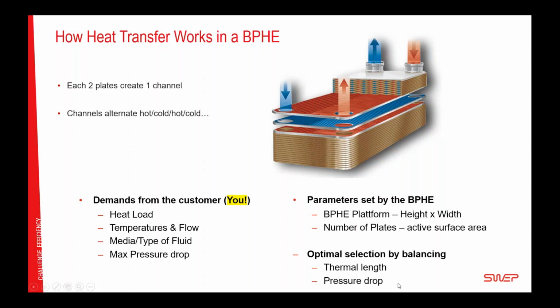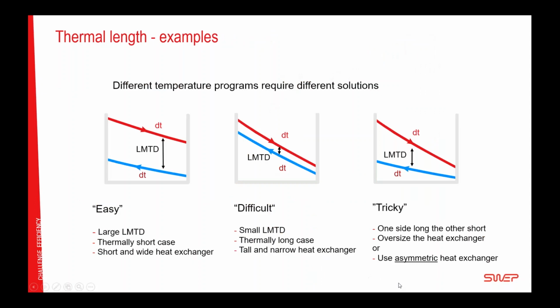And to know which platform to use and how many plates, we have to balance the thermal length and the pressure drop, which we will look into now. So what is the thermal length? We can categorize them into easy, difficult, and tricky. So we start with the easy one. What's an easy thermal length? Well, it is if the hot side and the cold side have a very big temperature difference. And we're measuring temperature difference in logarithmic mean temperature difference.